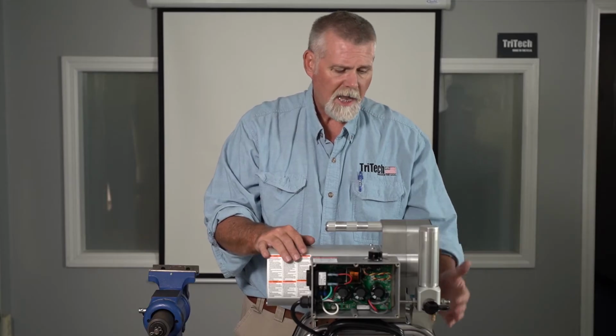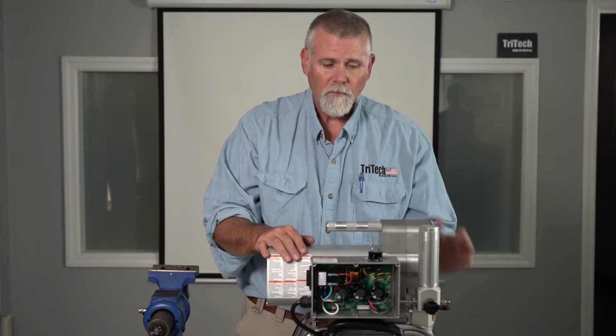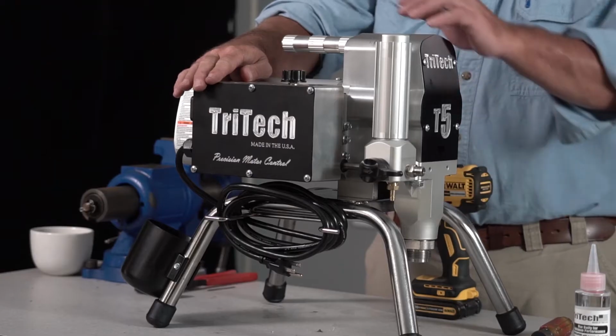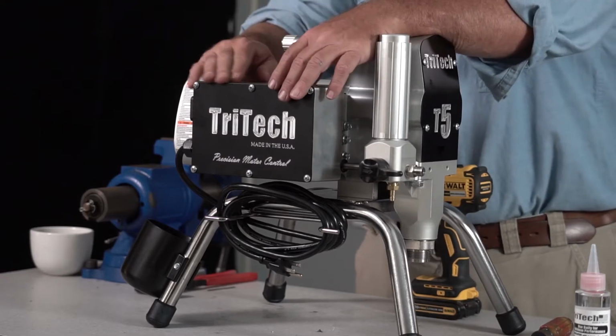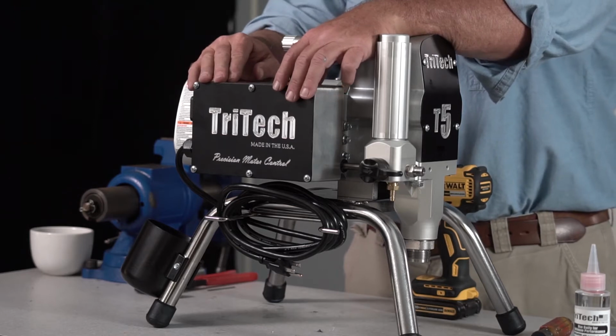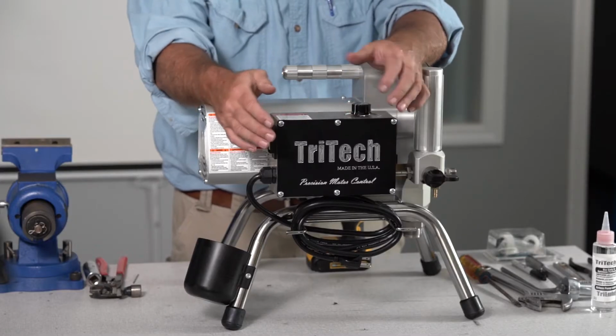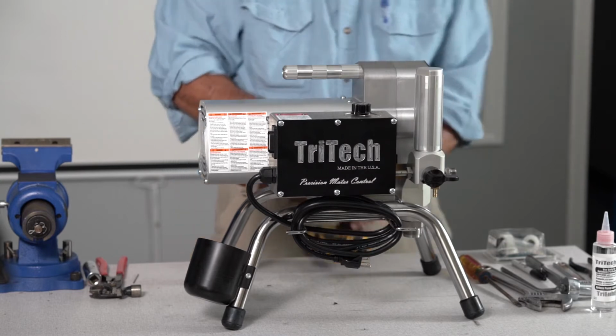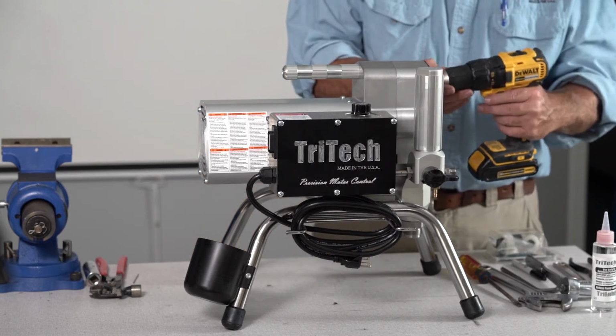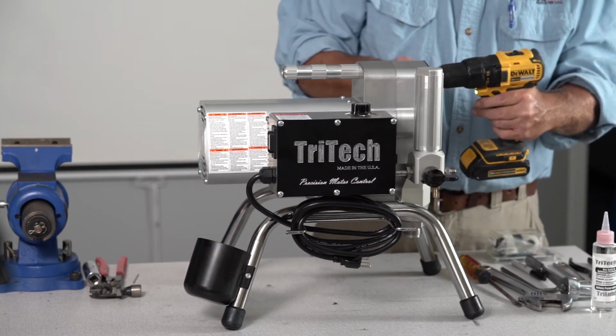So we're going to go ahead now and remove our fluid manifold from our pump. Side cover plate has been put back on. We want to make sure that this is protected. There's no reason to have this off during our repair, so we put that back on. Now, in order to pull the fluid manifold off, we have to take our front cover plate off.